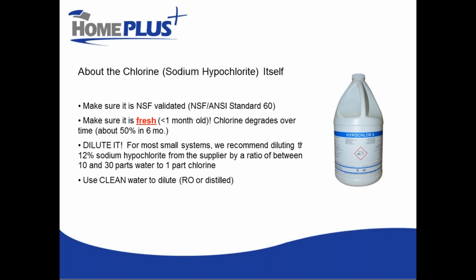Similarly, if you buy a 6-month supply of chlorine, the chlorine you use today should be nice and fresh. There's a reason that is bold in red and underlined. Fresh is really important. We try to shoot for chlorine that has been purchased within the last month, because don't forget, it might have sat on the store shelf for some time as well. If you have problems with one supplier, switch to somebody who has good, fresh chlorine. It definitely degrades and will not be the same as time goes on. It doesn't mean you can't use it as it degrades a little bit, but it means you might have to inject a higher quantity of chlorine solution to achieve the same result.